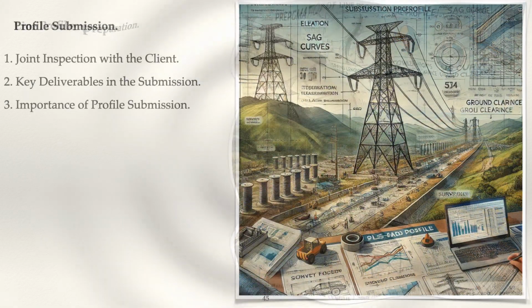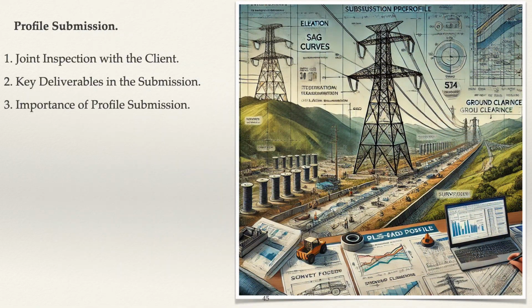Profile submission and approval. The submission of a transmission line profile to the consultant engineer, CE, and client marks a significant step in the project lifecycle. This process ensures that the proposed alignment, structural designs, and engineering details are reviewed, verified, and approved before proceeding to construction. Validation. The CE and client validate that the line profile adheres to technical, environmental, and regulatory requirements. Accuracy check. Ensure that the profile reflects accurate terrain data, tower placements, sag curves, and ground clearance measurements. Approval. Obtain formal approval for the finalized transmission line alignment and associated design elements, allowing the project to advance to execution.